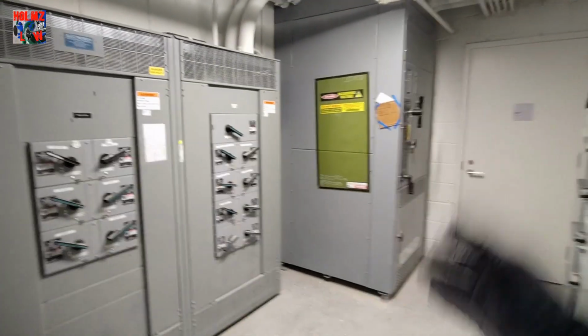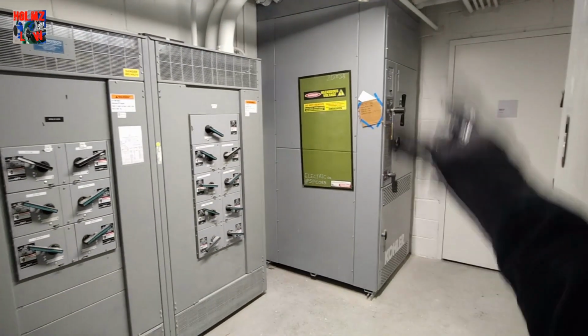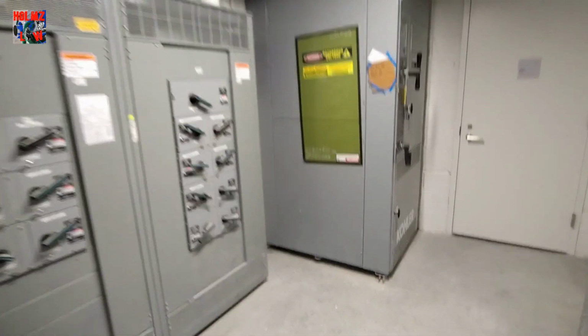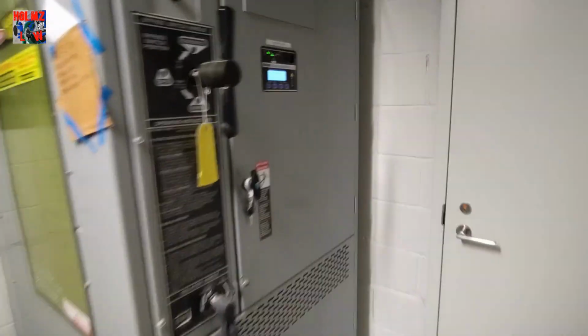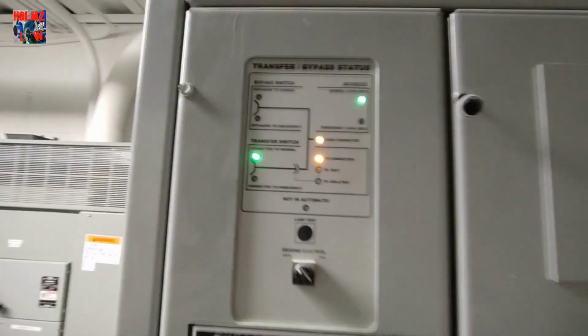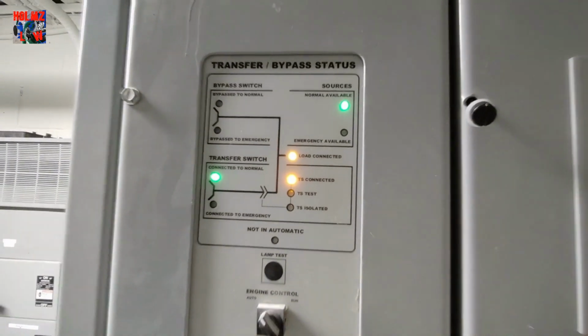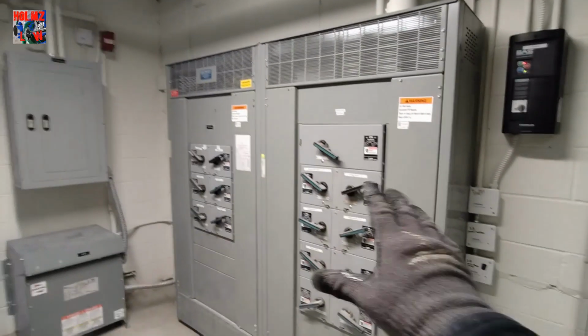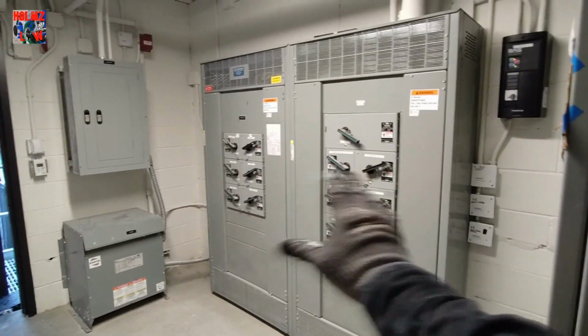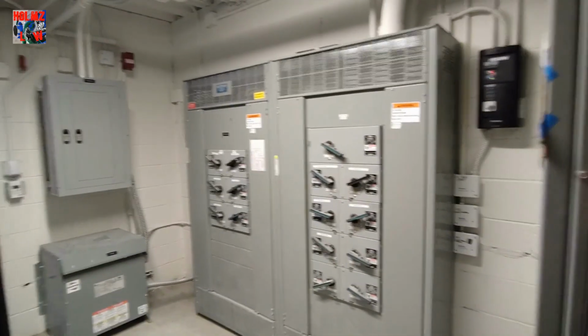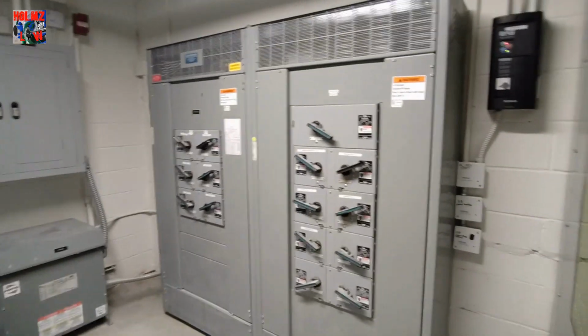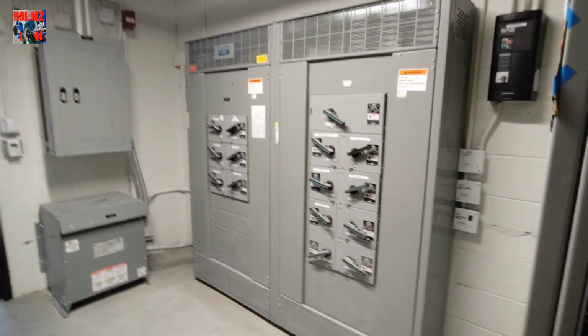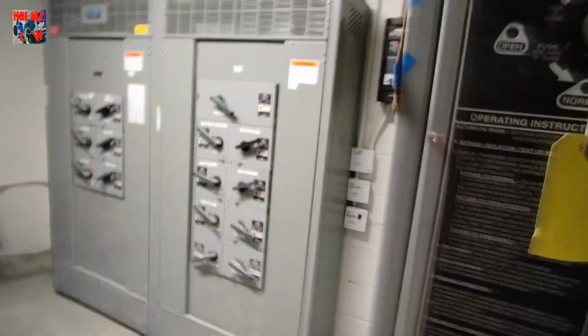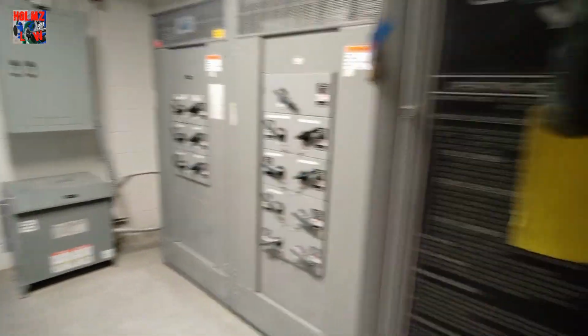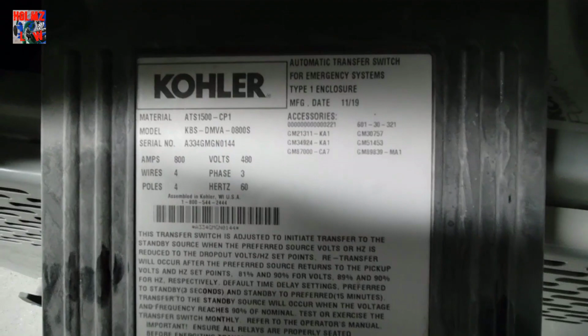It's also an actual bypass switch. That's why it's so big. It actually has two contactors in there, one for the ATS and one for the bypass. As you can see here, transfer and bypass. It's actually feeding this load here, which is a two section distribution, all the optional standby loads, and that is actually a four-pole transfer switch. Now, I could actually show you the nameplate to it as well. It's an 800-amp switch, four-pole, four-wire.